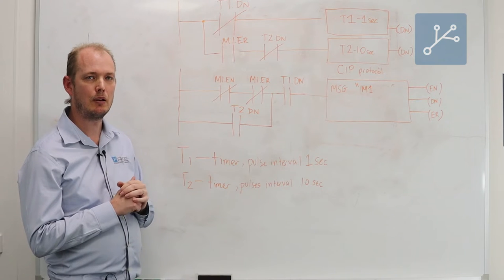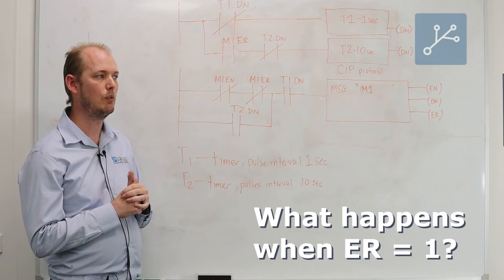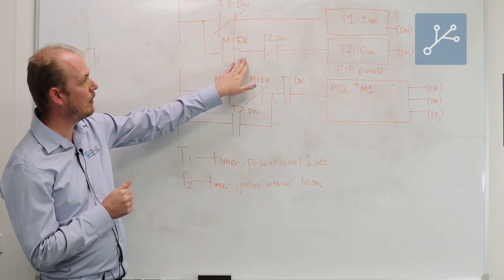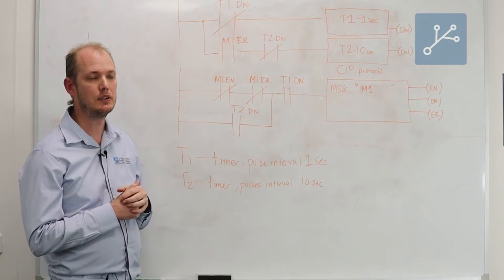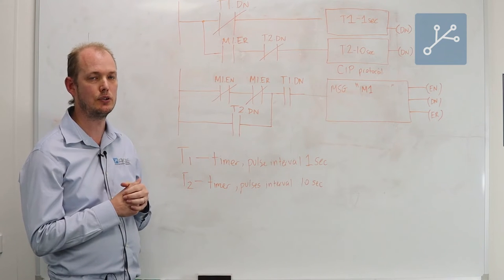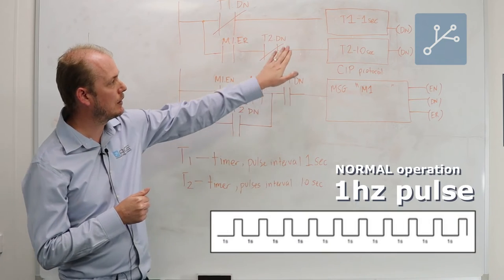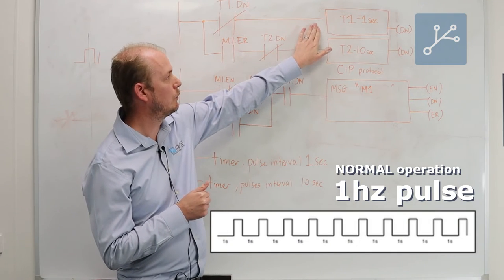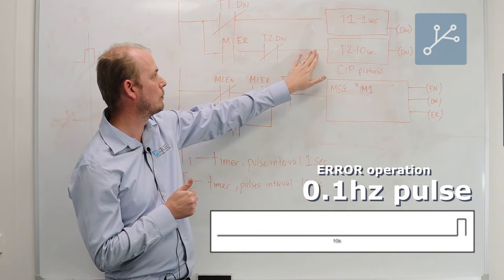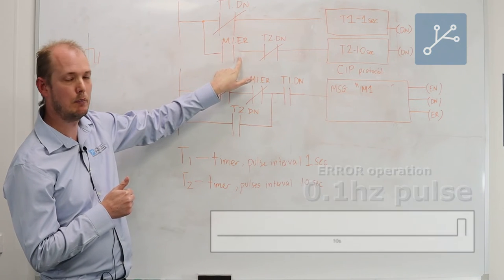So the question becomes: what happens when we get the error bit? What do we do? In this situation we have two timers which are controlling the speed or the interval between message execution. So we have a one second timer for normal operation and a ten second timer when there's a problem with the message instruction.